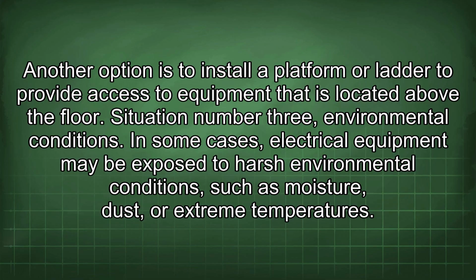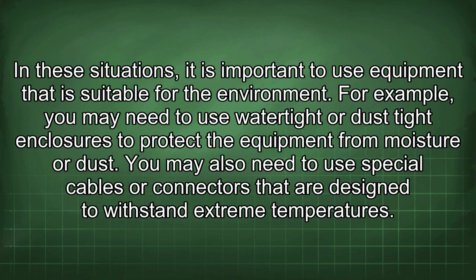Situation number 3: environmental conditions. In some cases, electrical equipment may be exposed to harsh environmental conditions such as moisture, dust, or extreme temperatures. In these situations, it is important to use equipment that is suitable for the environment. For example, you may need to use watertight or dust-tight enclosures to protect the equipment from moisture or dust. You may also need to use special cables or connectors that are designed to withstand extreme temperatures.